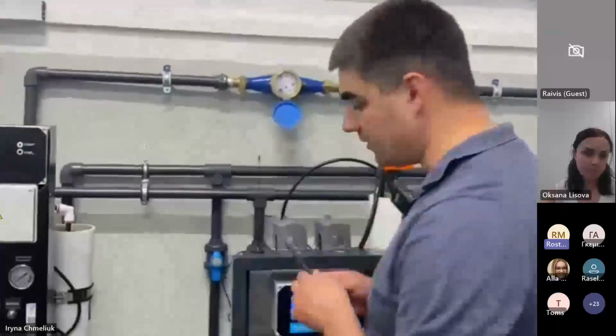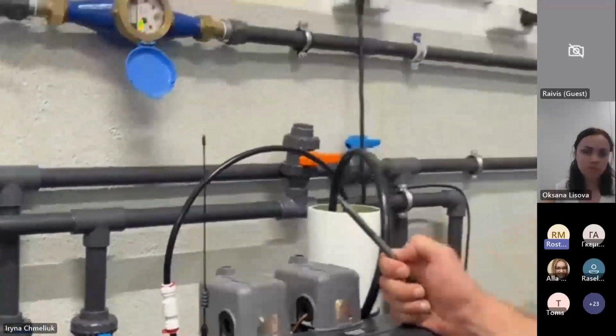Maybe there are questions on this part, on the pipe connections. Oksana, if you have any questions, please. Yes, Rost, just a very simple question, but it appears sometimes: what would happen if the size of the piping were not 1 inch? From time to time, it happens that if the connection pipe is not 1 inch, then very often we might have an issue with no water.